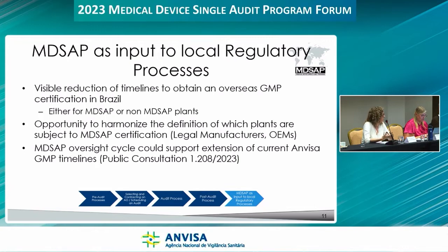We do see an opportunity to harmonize the definition of which plants are subject to MDSAP certification, which we were just talking about a couple of minutes ago. Are they extended to legal manufacturers, to subcontracting? This is probably one of the points where some of the companies that are required to have a GMP certification for the registration of their products in Brazil are not necessarily covered by MDSAP.